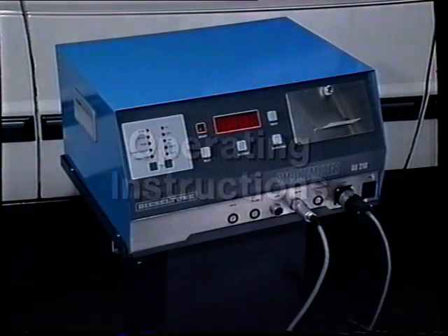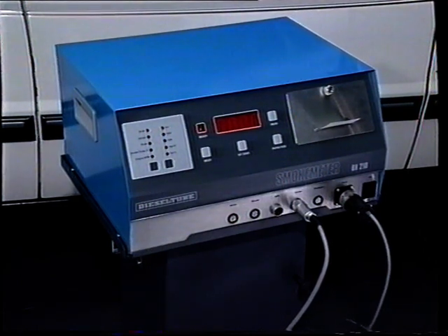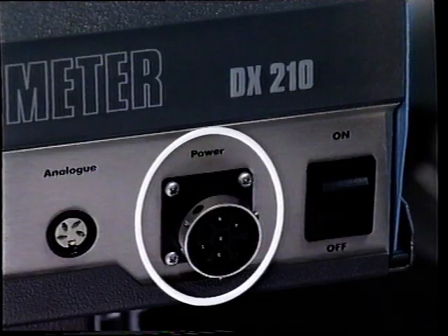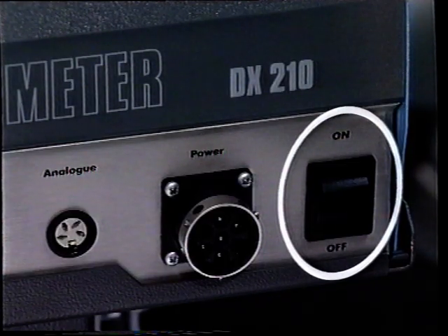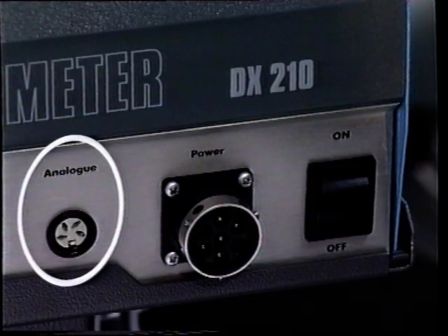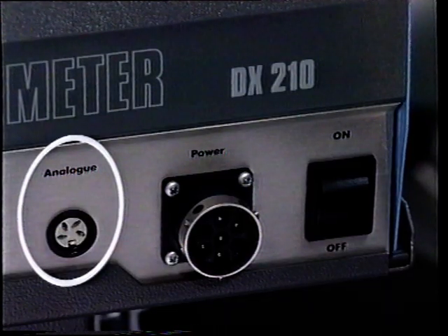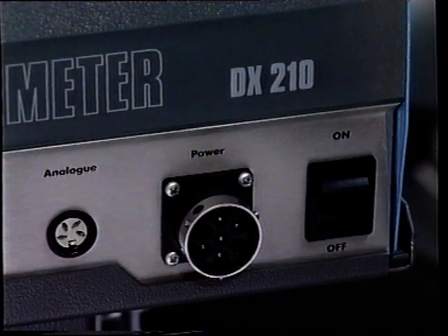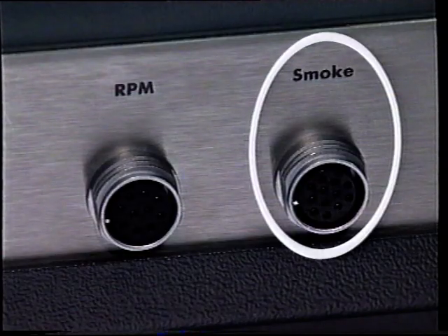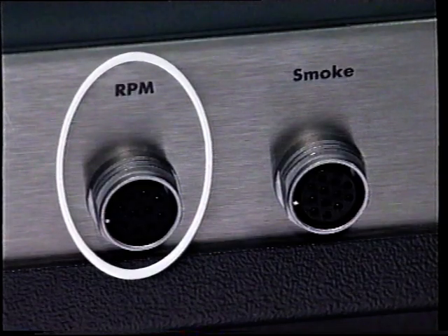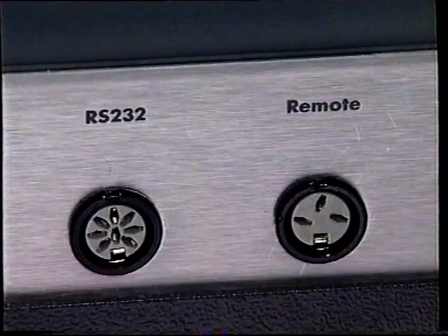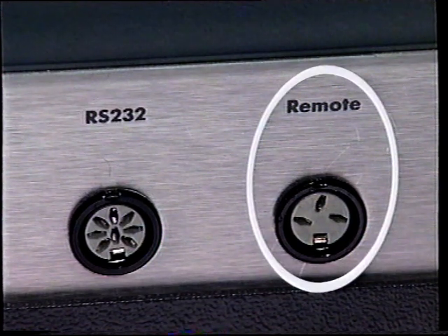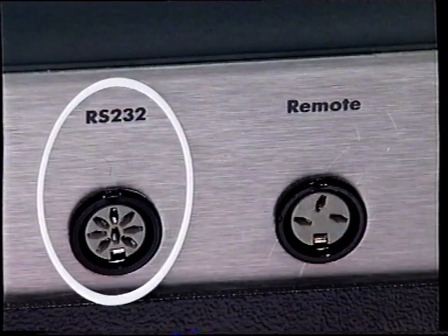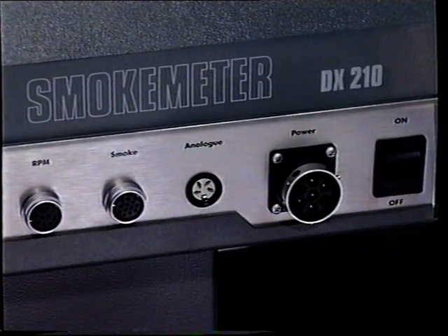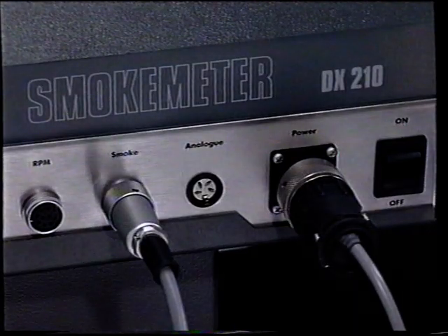Let's start by briefly looking at the connections on the front panel. This socket is for the main supply cable into the unit, and next to it the on-off switch. Moving to the left is an analog output, which will only be required for certain special functions, such as driving a pen recorder. This next socket is for connection to the smoke sampling head, and adjacent to that is the input socket for an optional RPM sensor. The 2 final sockets are this one for the remote reset cable and this for connection to a personal computer. So, with the necessary leads connected, you can start the test.